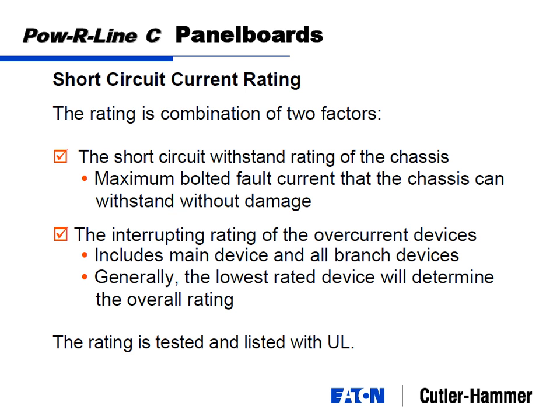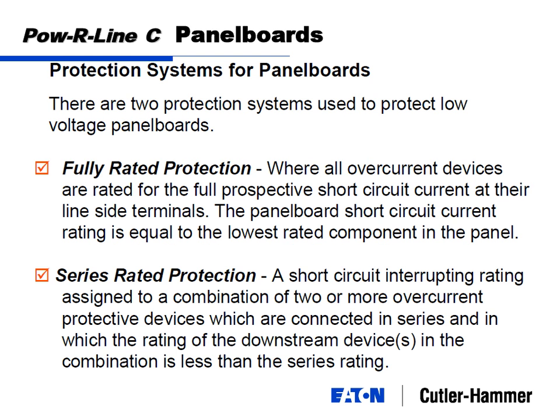And generally, when we talked about fully rated and series rating, fully rated means all the circuit breakers in that panelboard have to be able to interrupt that 65,000 amps. Now looking at the other one that we didn't necessarily touch on yet, series rated. Your fully rated is where all the devices have to be rated for the short circuit rating at that panelboard location. A series rating is a short circuit interrupting rating assigned to a combination of devices, two or more, basically two or three, in series, in which the rating of the downstream device in the combination is less than the series rating.